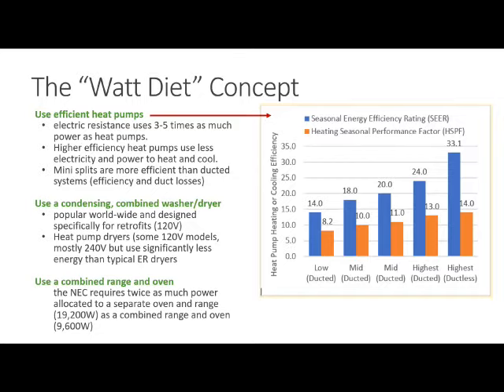There are also heat pump dryers. There are some models that are 120 volt, but they're mostly 240, and they do use a lot less energy than a typical electric resistance dryer. Also, one of the strategies in our examples is using a combined range and oven. The NEC requires twice as much power if you do have a separate oven and range, which conceptually makes sense than if you have one system, a range and an oven combined in one. The power allocation to that device is less overall.